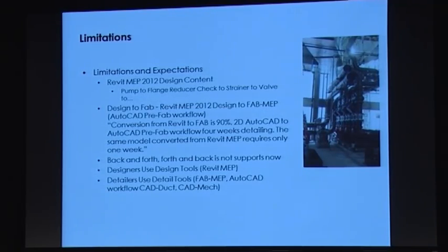So some of the things that you need to think about: if you are trying to do this pump header and you don't have that exact dimensional data for all those components, don't expect all that stuff to be perfect. The design models that are coming out of Revit MEP 2012, that pump's not completely satisfied yet. Those type of things have been lost in the past without standards. Now there's a standard that says this pump is not approved yet by the manufacturer. This is not fabricatable yet.